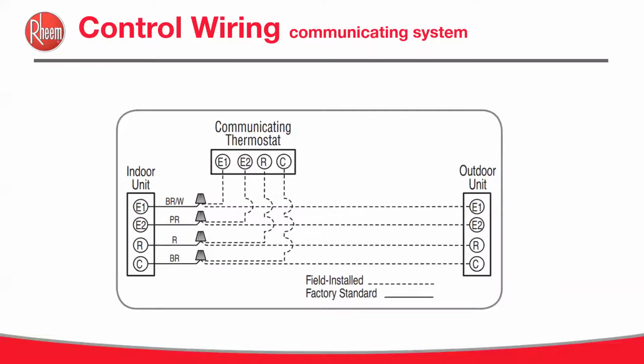With the communicating systems, the newer, more advanced systems with the EcoNet, the control wiring consists of only 4 wires. Yes, it's that simple. E1, E2, R, and C, from the communicating EcoNet thermostat to the outdoor unit. This doesn't matter if the system is an RA 17 or 20 air conditioner or an RP 17 or RP 20 heat pump. So it doesn't matter if it's a heat pump or air conditioner, it's as simple to wire both.